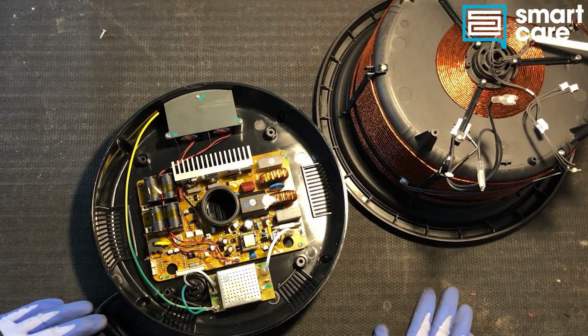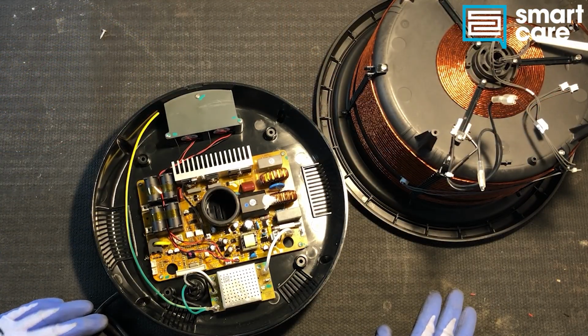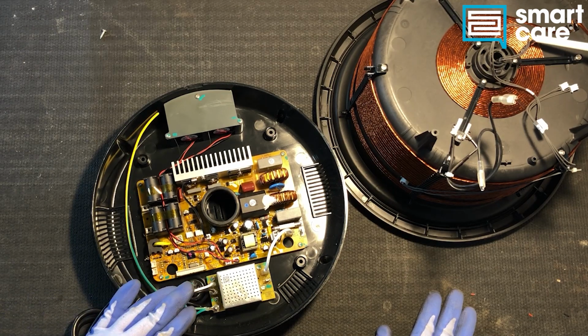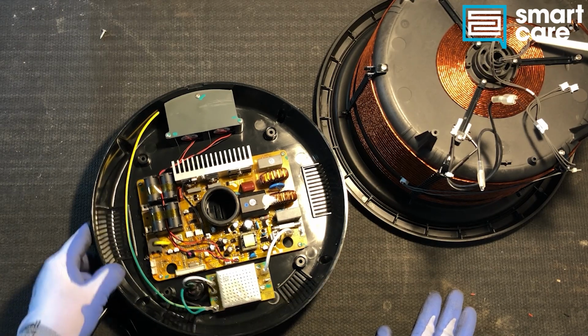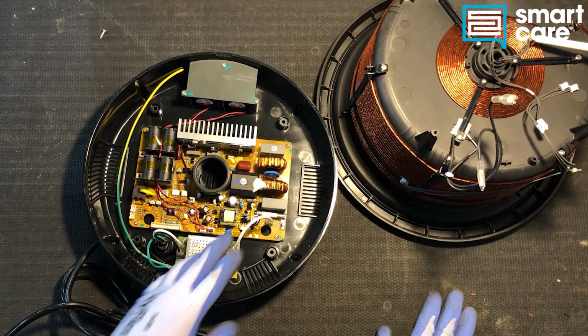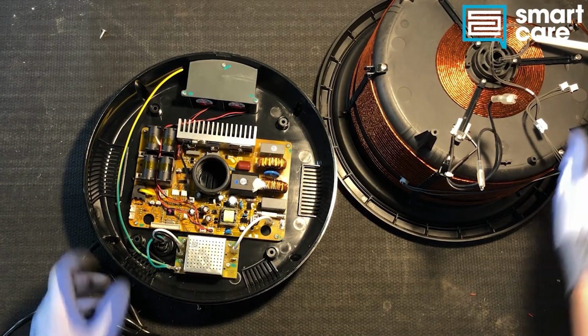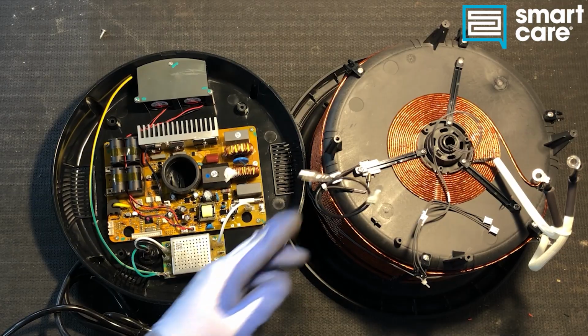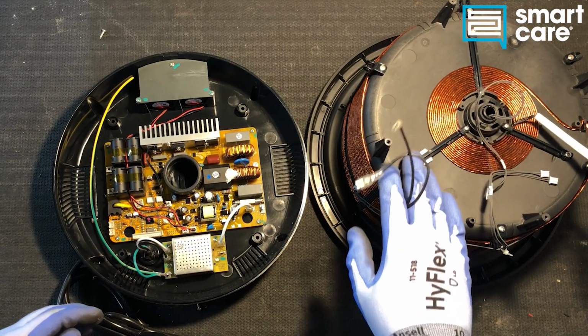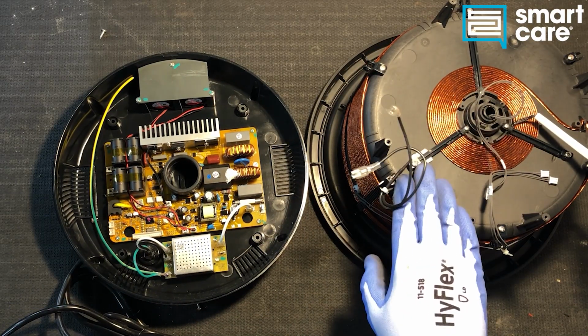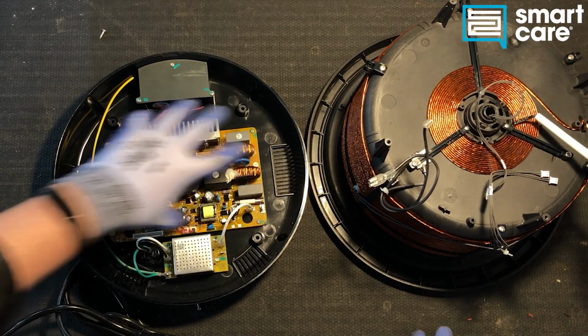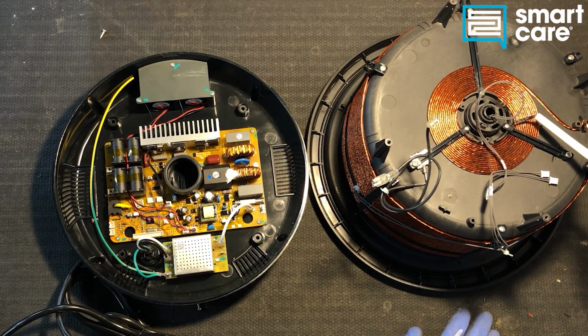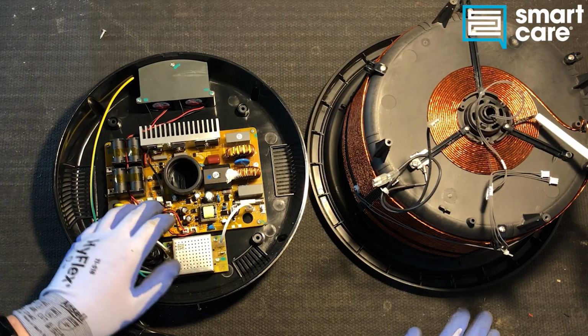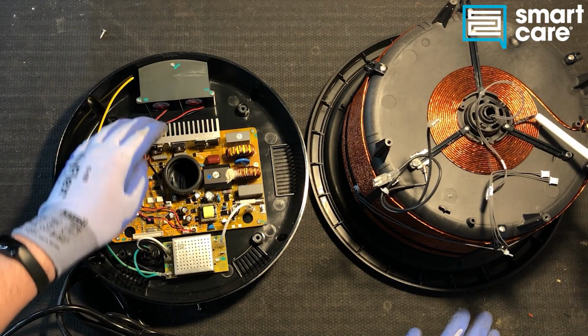Taking a look down at this part, you can see we've got the incoming power coming into what looks like a power supply board, and the output from that runs through whatever this thing is, which reinforces my belief that it's some kind of high limit safety mechanism. So if this were to open, all the power to our driver control would cut off. The driver itself, you can see it's got a couple of cooling fans and some heat sinks.